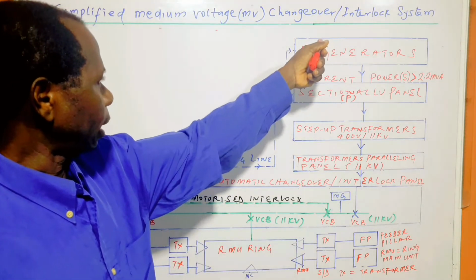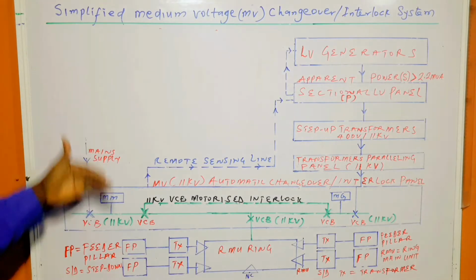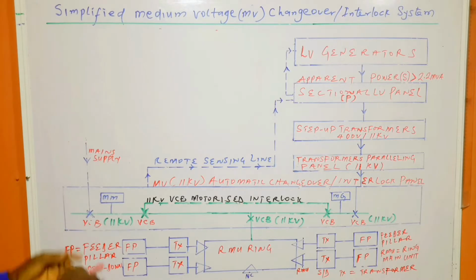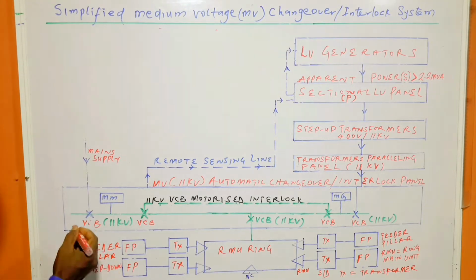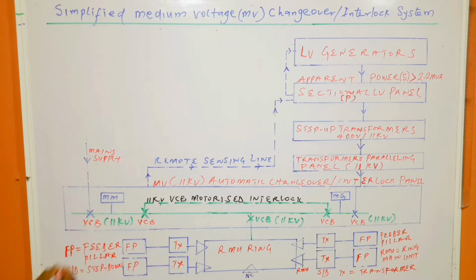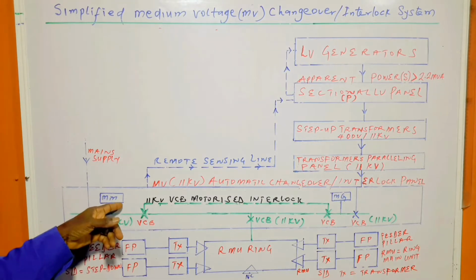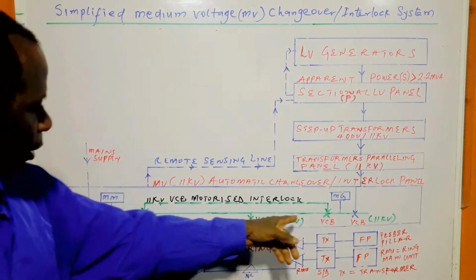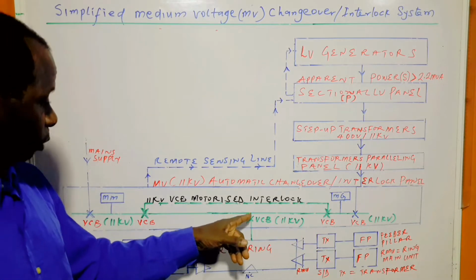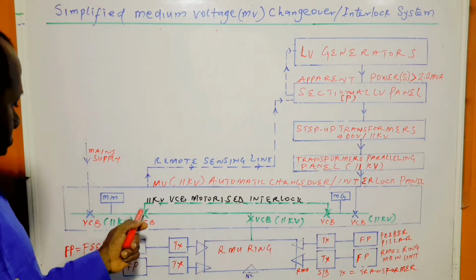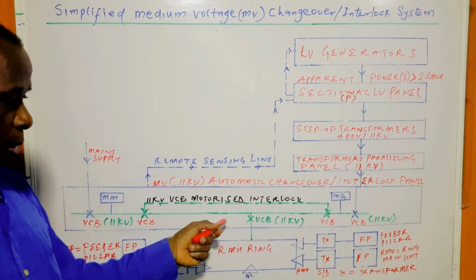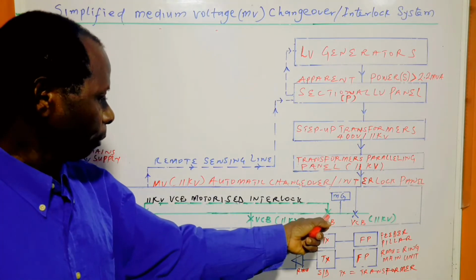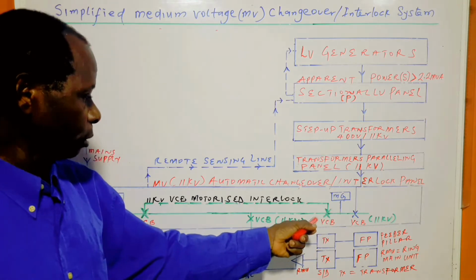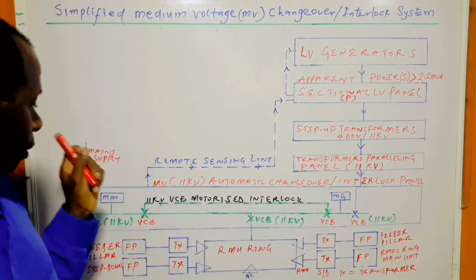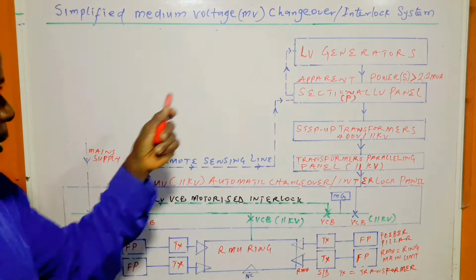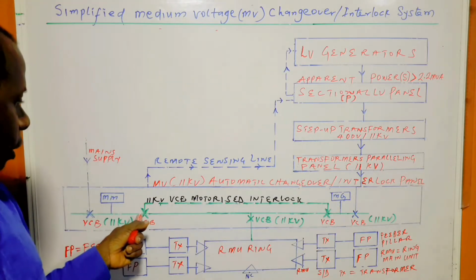Now let's talk about the main supply. Here we have the incoming circuit breaker, which is also a vacuum circuit breaker, VCB, at 11 kV. Then we have a mains metering unit, and then the interlock, which is in green color here. This is the output of the interlock, and this is the common bus section. If it is this one that closes, power is delivered to this common bus section. And if it is the generators that are working, power is also delivered to this bus section. But the two circuit breakers will never close at the same time. When there is no supply from the mains, this one will close and this one remains open.